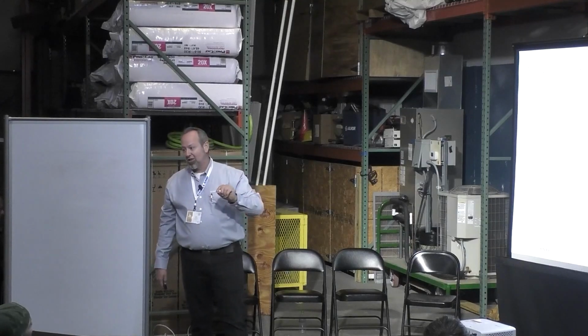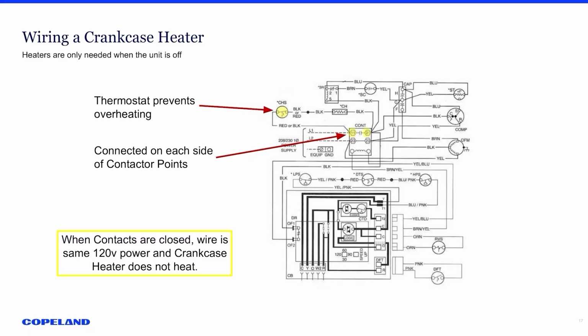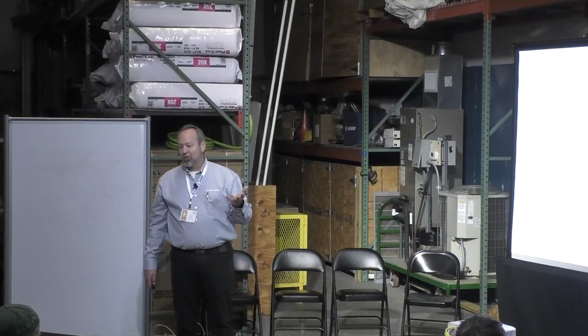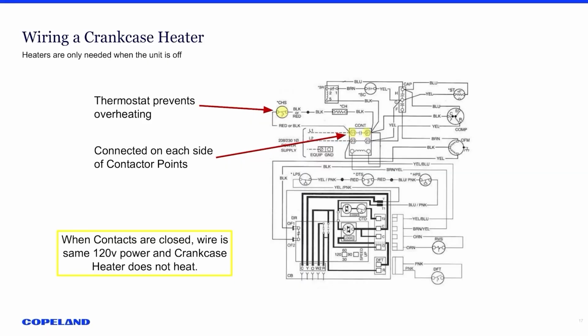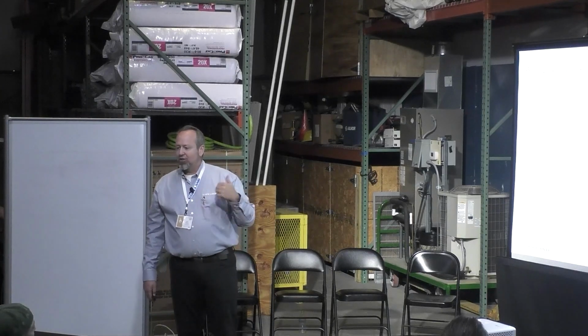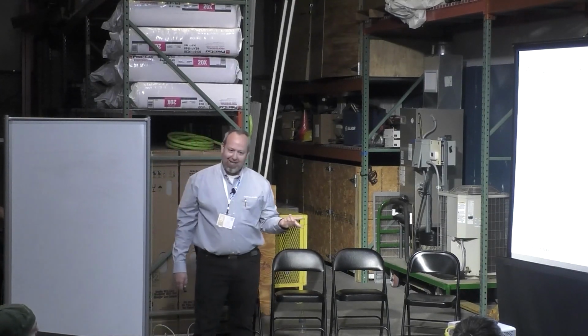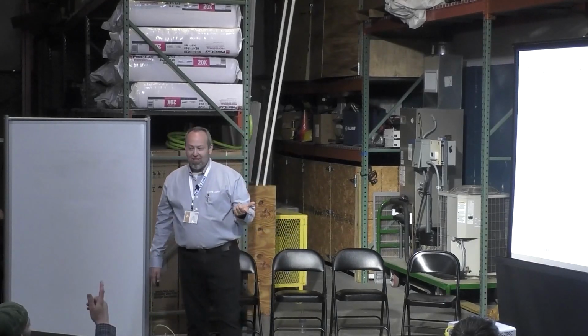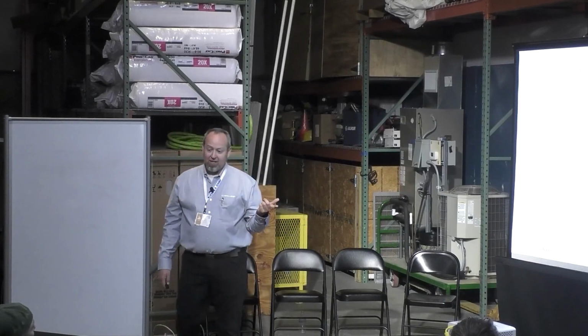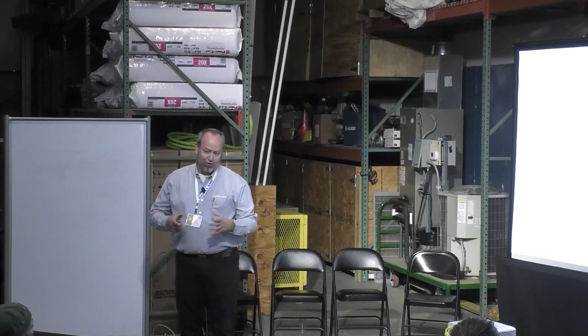Once the contacts close, that whole line is now L1, and two wires on L1 have no resistance. You're not going to have a heater functioning when it's running. So by wiring it on each side of the set of contacts on a contactor, it's on when the compressor's off, and it's off when the compressor's on. And it saves that crankcase heater from being on when the compressor's making its own heat.